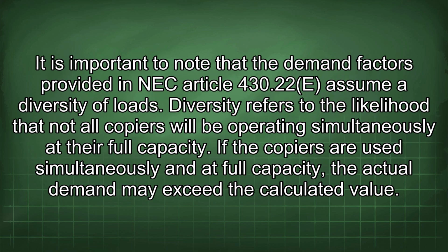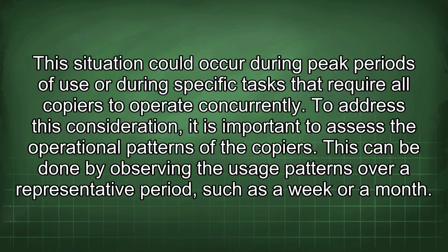It is important to note that the demand factors provided in NEC Article 430.22(e) assume a diversity of loads. Diversity refers to the likelihood that not all copiers will be operating simultaneously at their full capacity. If the copiers are used simultaneously and at full capacity, the actual demand may exceed the calculated value. This situation could occur during peak periods of use or during specific tasks that require all copiers to operate concurrently.